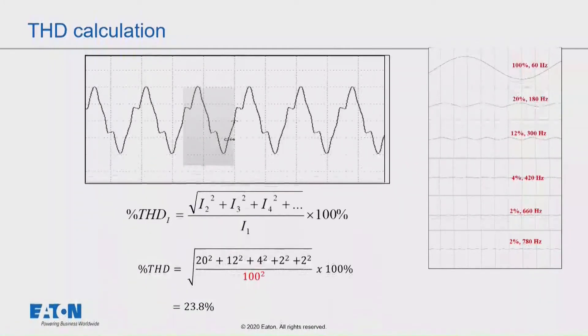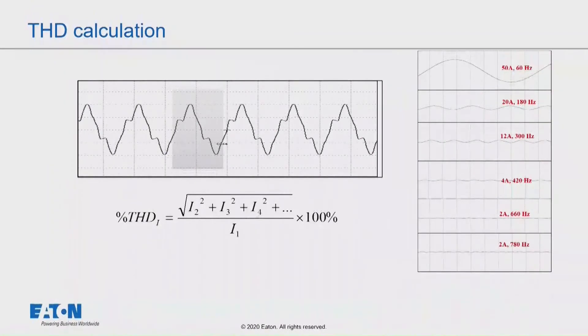Now, let's see what happens if I change the fundamental current. So instead of having 100 amps, I have 50 amps. If I keep my harmonics the same, the third, fifth, seventh, eleventh, thirteenth, the distortion value, the percent distortion, is now double what it was before.